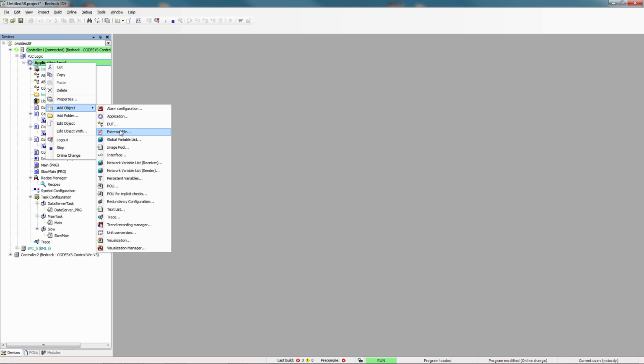the controller itself. If there's a change of this file in any of those 3 locations, then there'll pop up a menu to allow the file's contents to be synchronized between those 3 areas. And once the file is on the controller, then you have read-write access to that from your application program. So that would be another way you could do recipes or something along that line, get external information into your project and make it persistent.